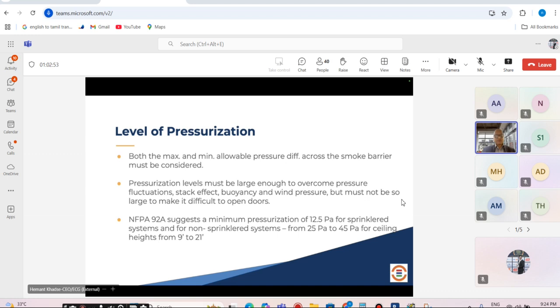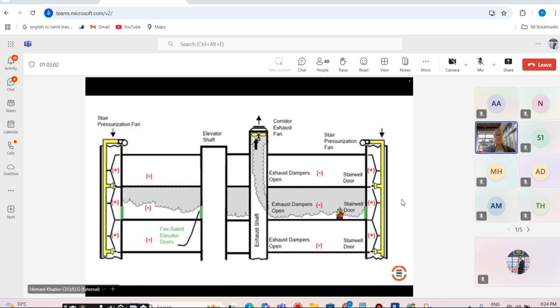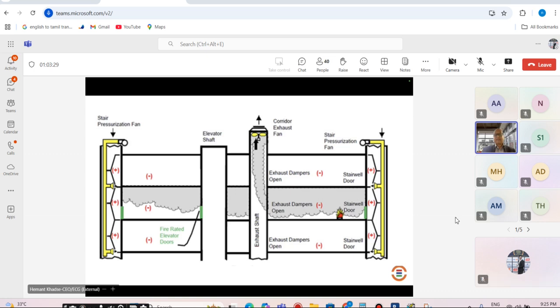ASHRAE also has a very good manual which addresses the smoke management techniques and principles. That's how your systems are going to be designed, as I mentioned to you. But the whole point that I want to elaborate here is that when you look at all the applications in your codes and standards, you have to see how it is going to be more effective for that particular project, and at the same time practical. At times I have seen in many places where the pressure system is installed, but it has never been maintained well, it has never been checked periodically, and the operator doesn't even know what the differential pressure of that staircase pressurization fan is right now, after 5 years.